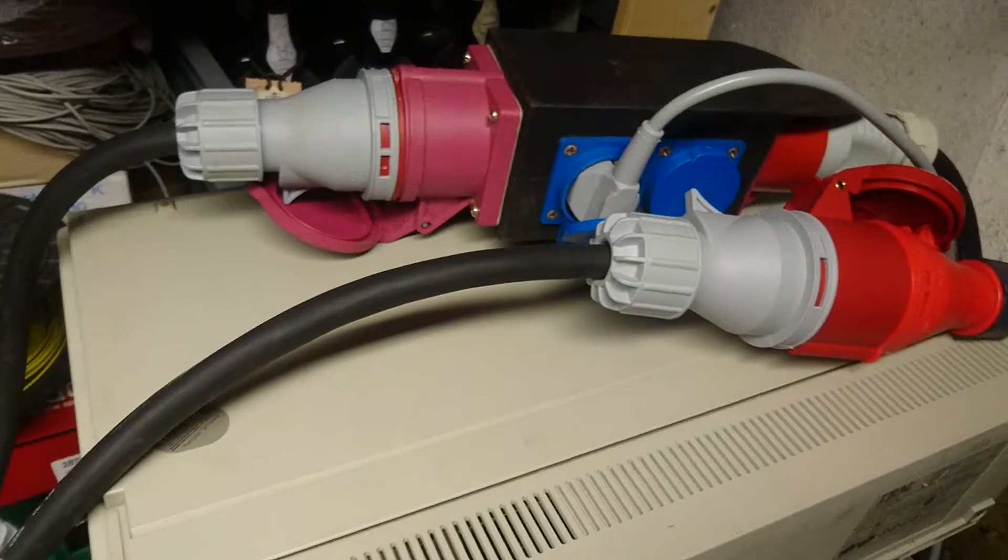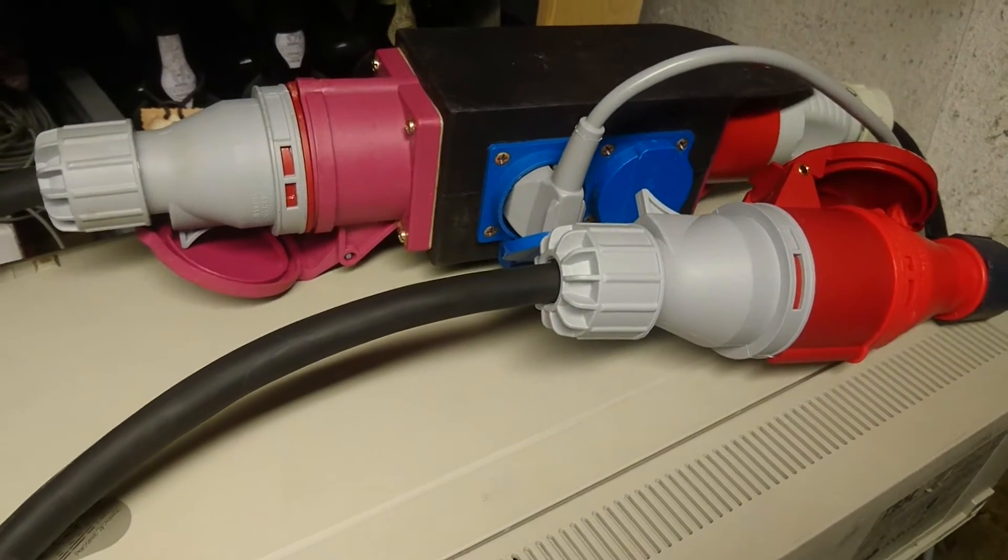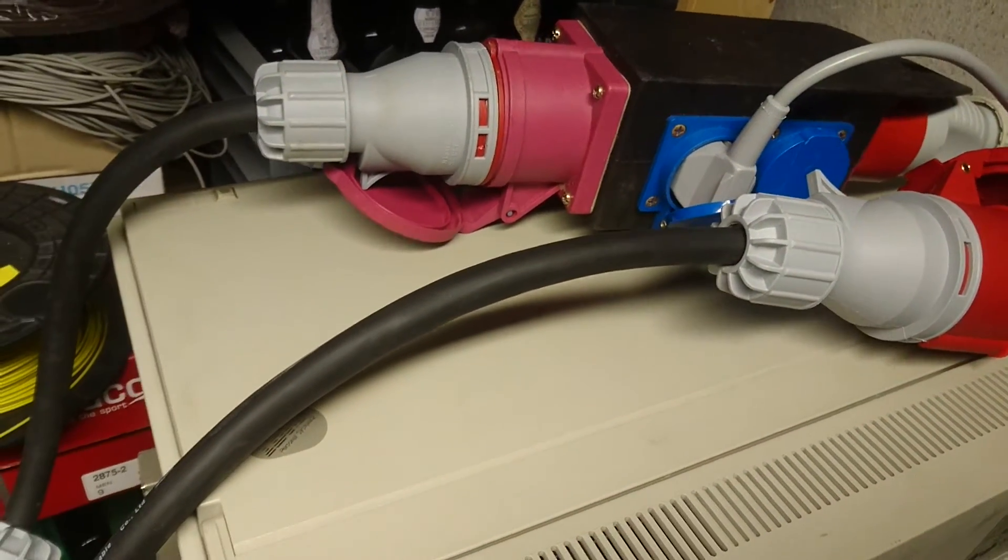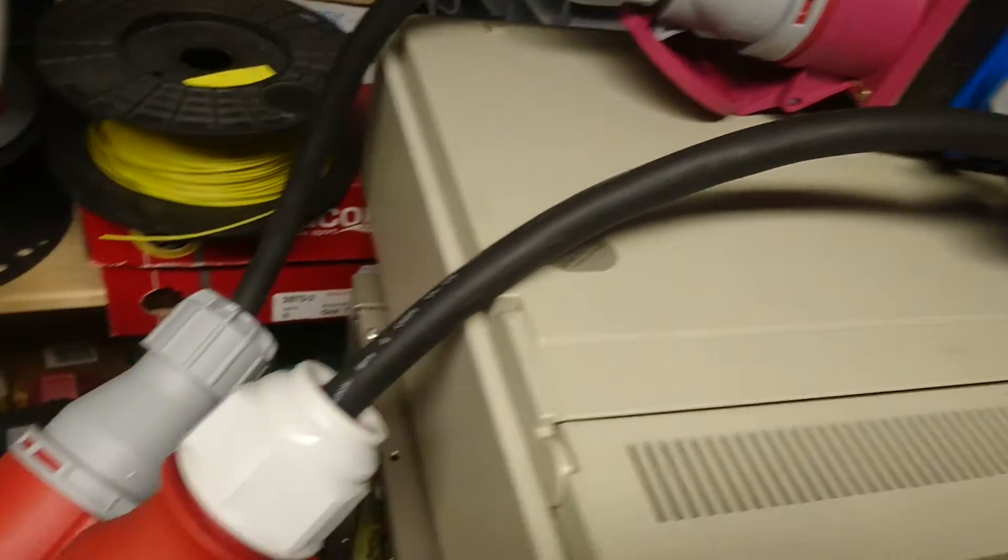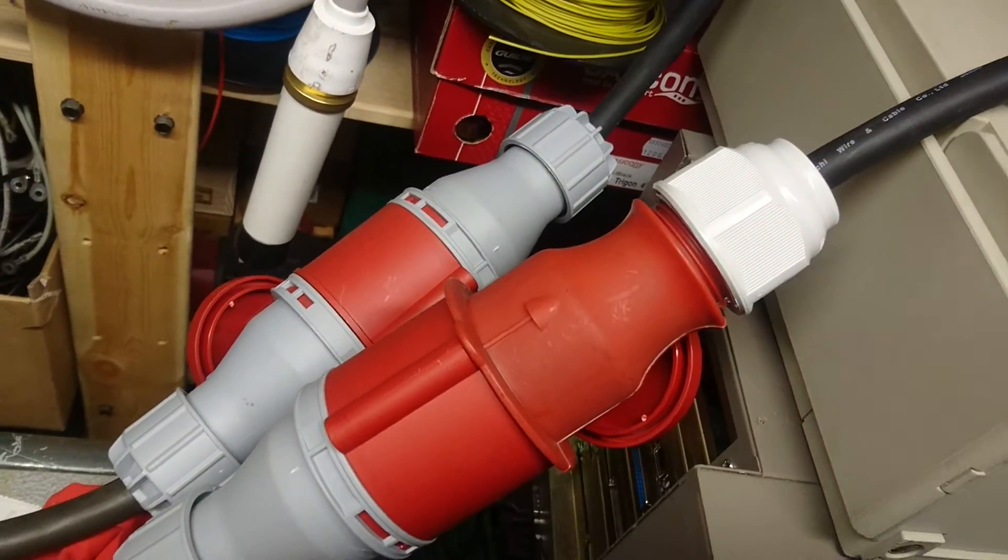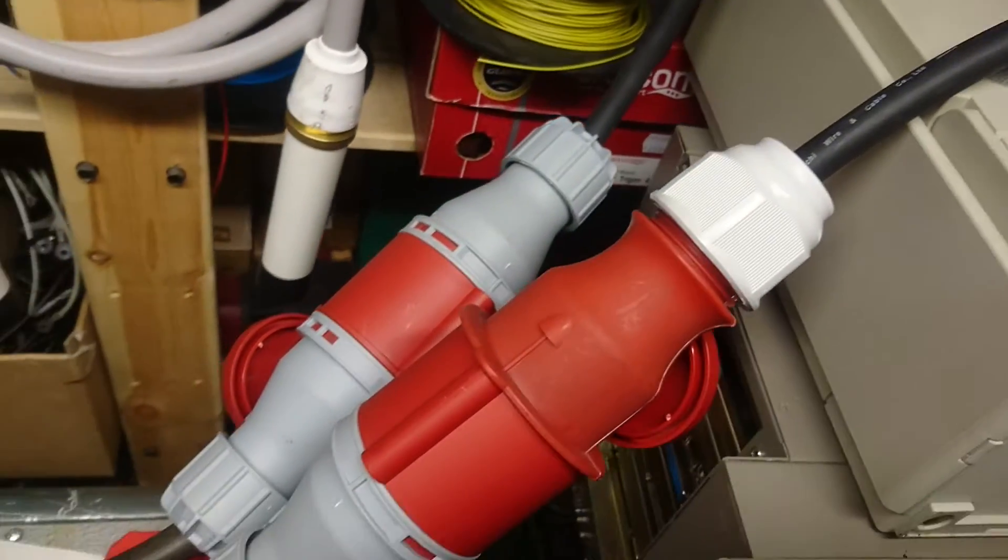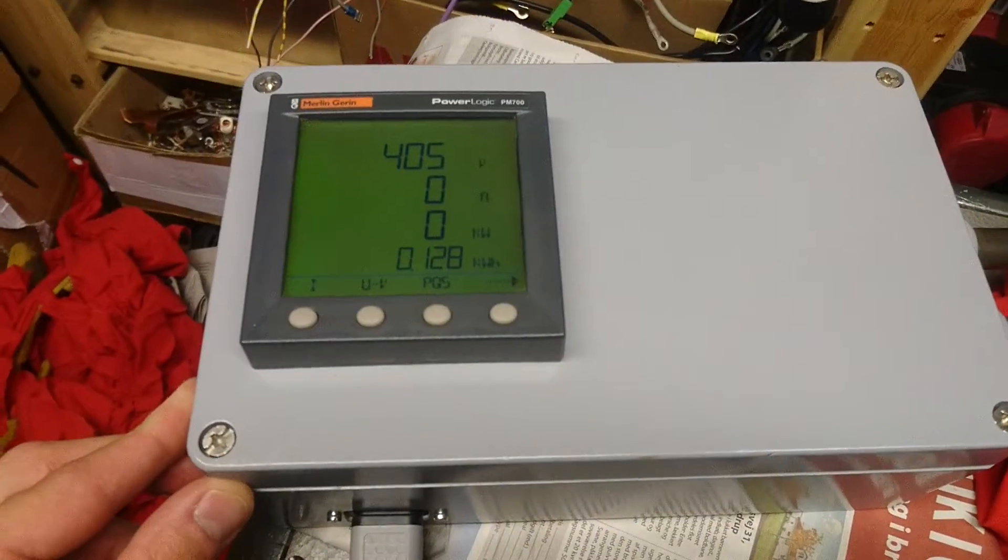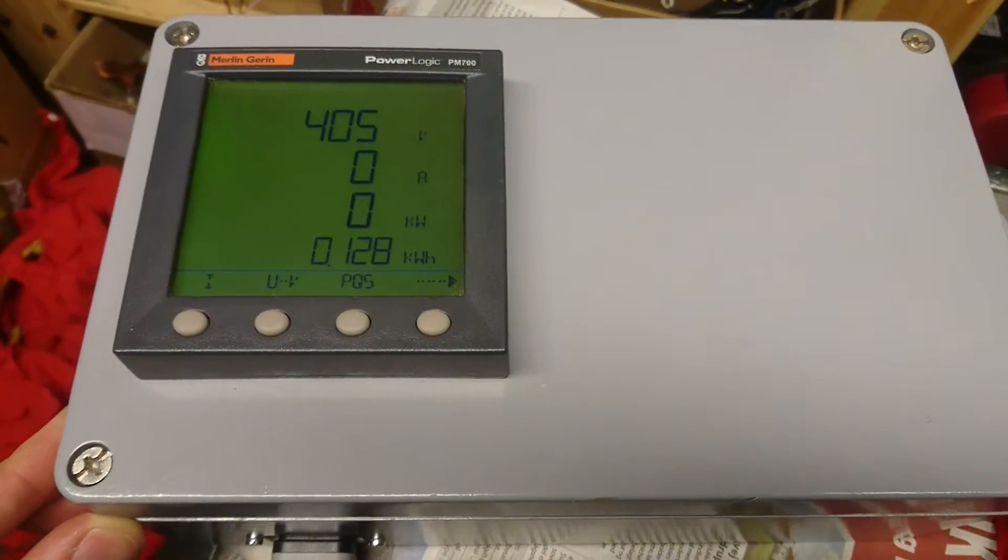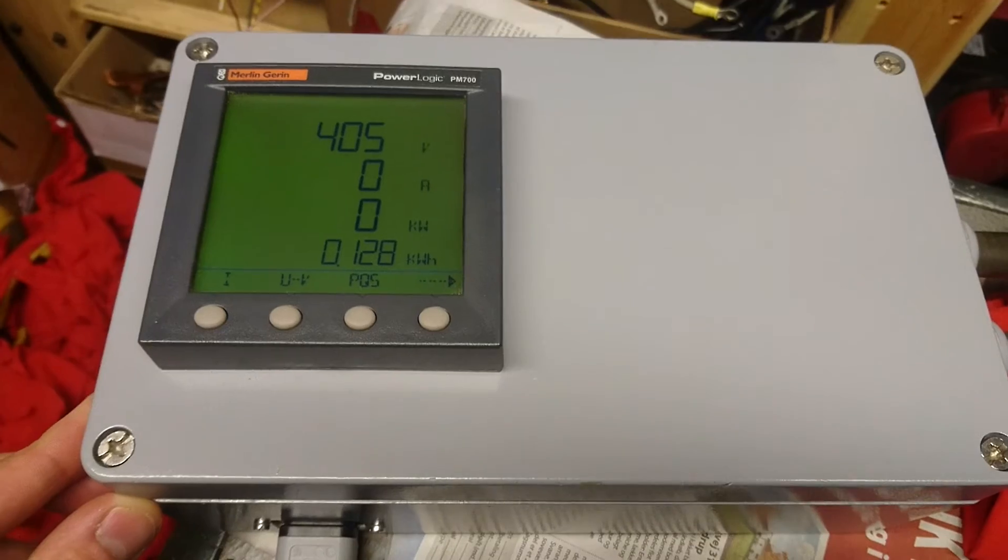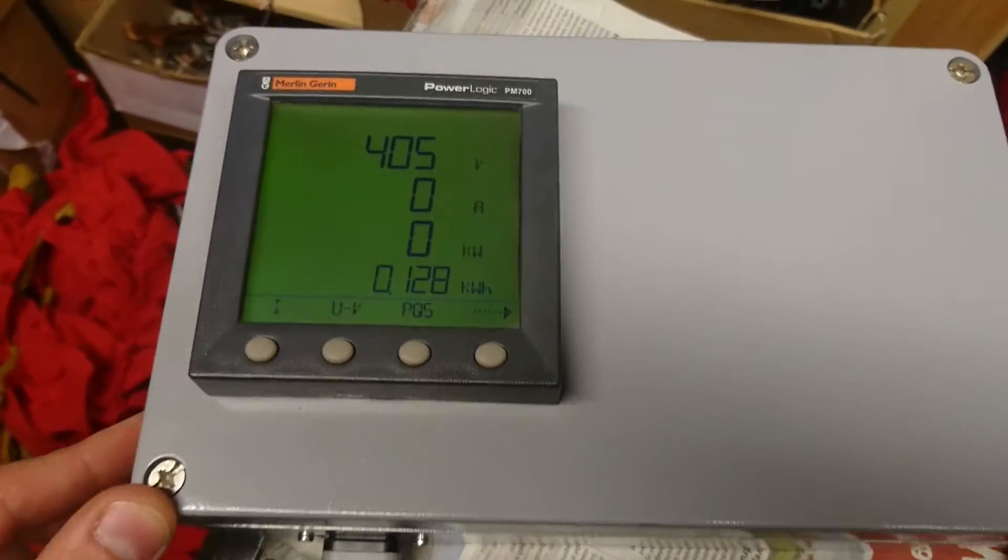I made this so it could be used with up to 32 amp CEE connectors, and with a few adapters I can also use this with 16 amps, which is legal. Adapters are not illegal in themselves, it is just illegal to use adapters without a suitable fuse in front of the cable size.